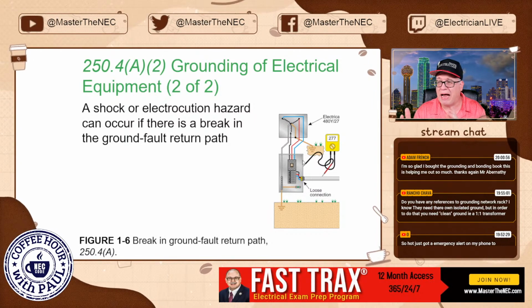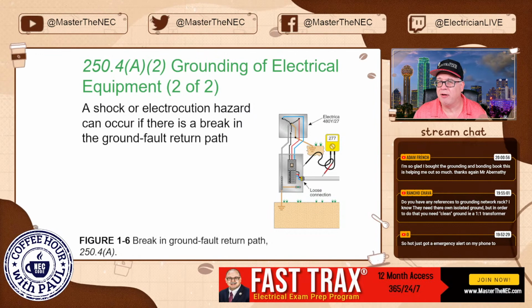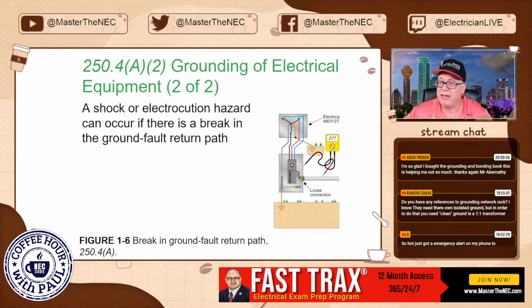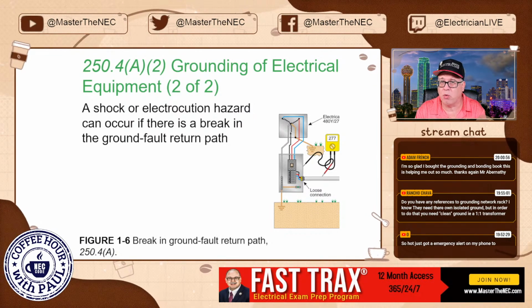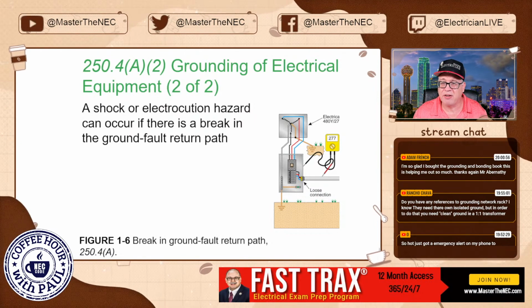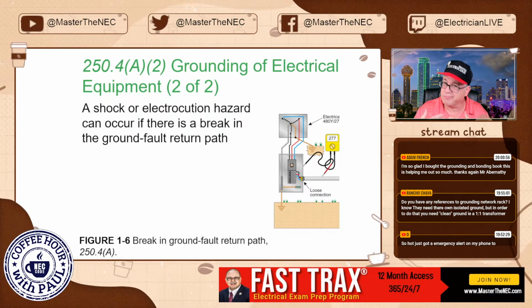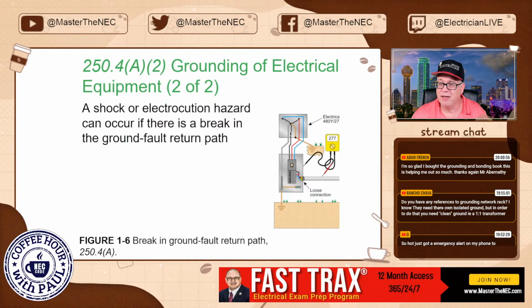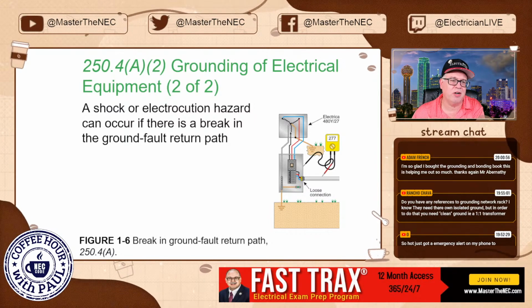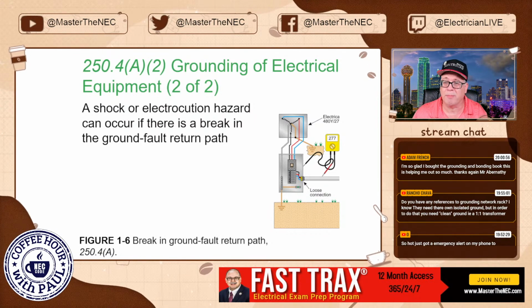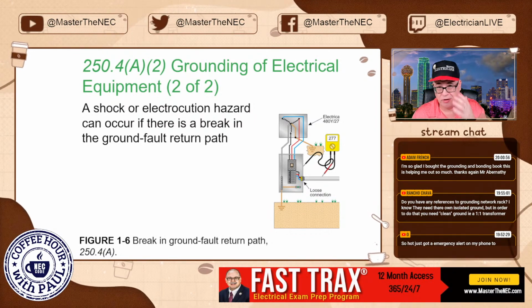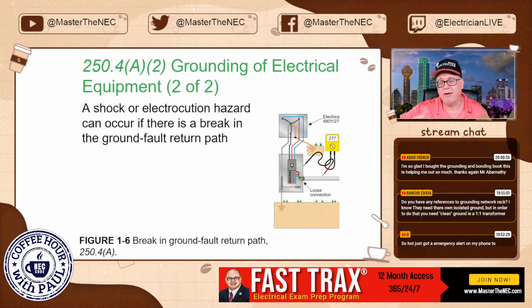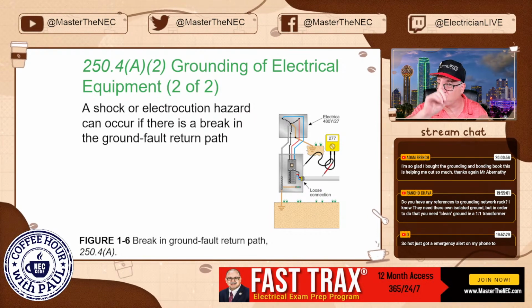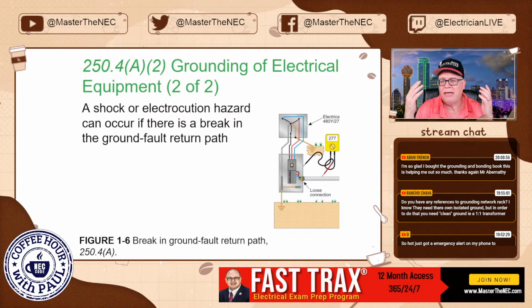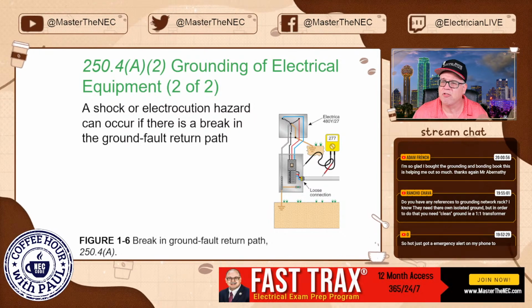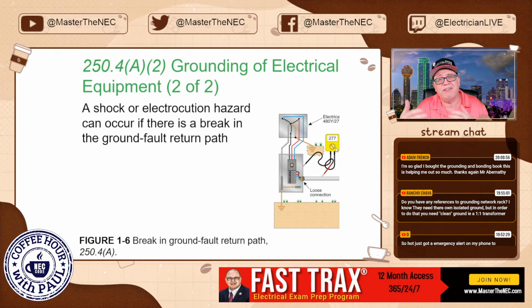And if this is near combustible material, well, heaven forbid. That's why when you go into hazardous locations, we have so many other rules you have to follow in Articles 500, 501, 502, 503, because that arc from a loose connection could be catastrophic. Again, most engineers, and most electricians, will want to pull a wire type equipment ground in there. But with 250.118, when we get there eventually in this series, make sure you're subscribing. We can't learn it all in one night, folks. We've got to have a little fun with this, and I get to sit with you and have this time together.